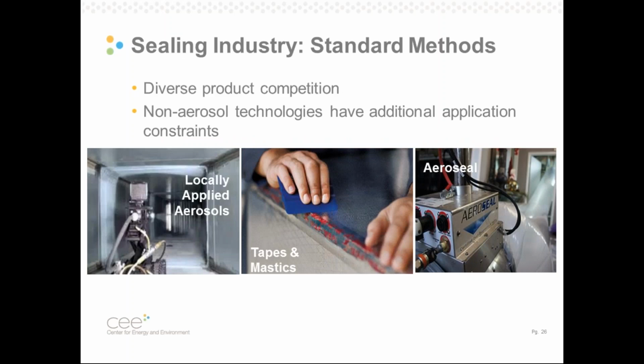And it turns out that there's a lot of ways that we could go about retrofit sealing ductwork. We have conventional methods, which are in line with how ducts have traditionally been sealed for a long time. These include applied spray sealants, painted on or sprayed mastics, and then tapes on seams. They've also got a little robot that you can put through ducts that will traverse a horizontal section and spray sealant from the inside. And then we have this new process that was very convenient for our project and for retrofit duct sealing opportunities, based on an aerosol sealant that's delivered from the inside.